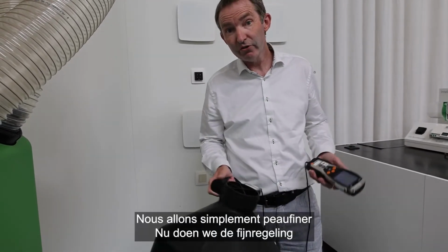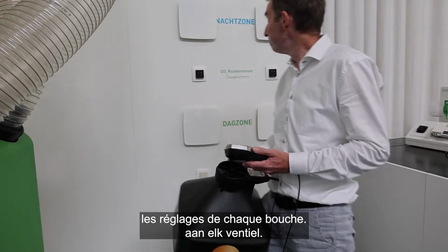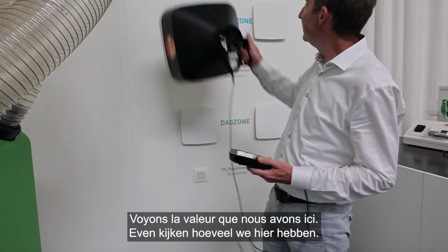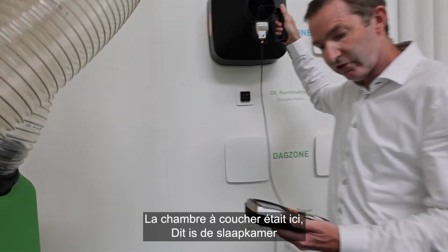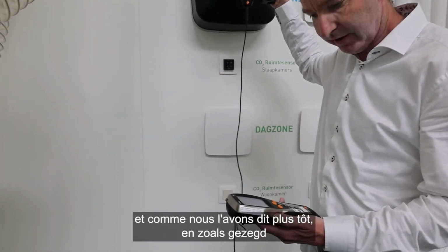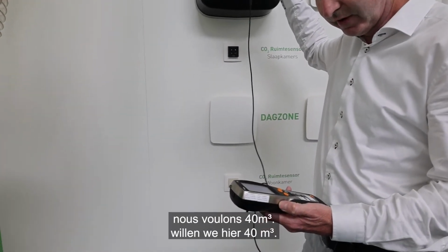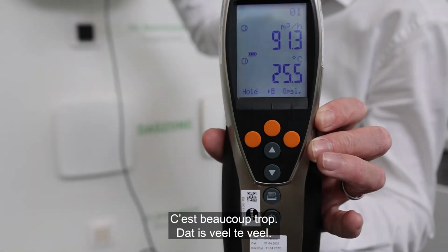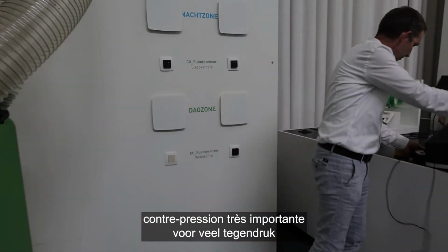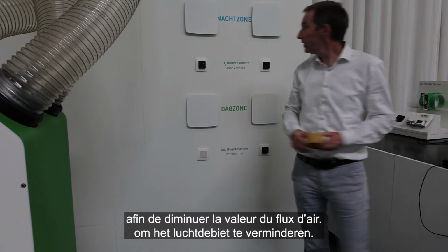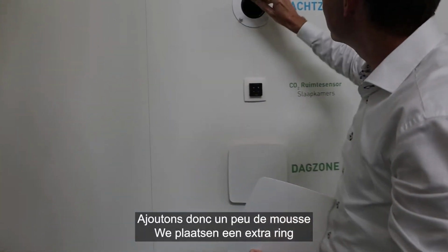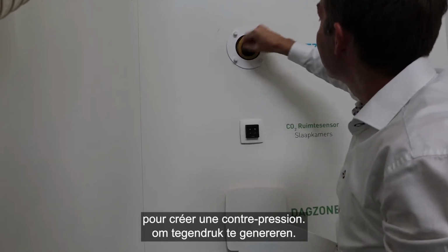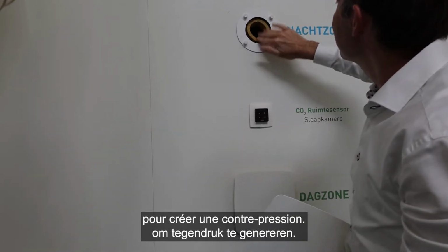Now we actually do fine-tuning at every vent. So let's see how much we have here. So this was a bedroom, as we said earlier, and we wanted to have 40 dB. Well, at this particular point I have over 90, so that's way too much. So I need to create a lot of counter pressure here to make it go down. So let's put in some extra mousse to create some counter pressure.